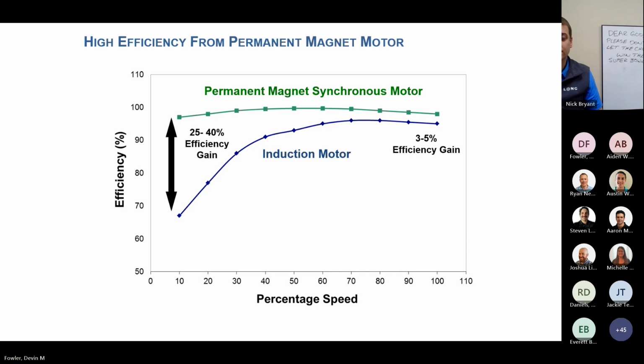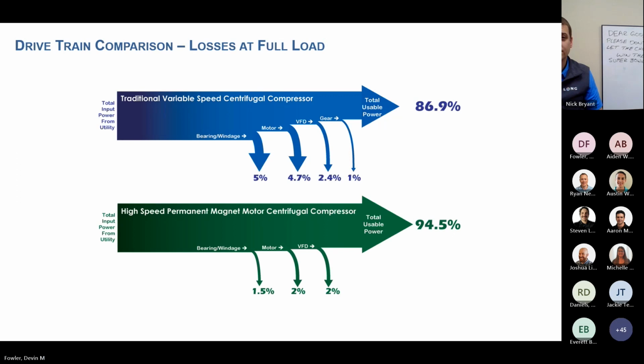centrifugal machine. To even further these savings off of these losses, when comparing a traditional speed centrifugal compressor with a magnetic bearing and magnetic motor compressor, we can take our bearing and windage losses from around 5% to 1.5%, our motor losses from 4.7% to 2%. With the specially optimized VFDs that we use on these chillers, we can take our VFD losses from 2.4% to 2%. And with eliminating the gears in our drivetrain, we no longer have that 1% loss to the gearing.